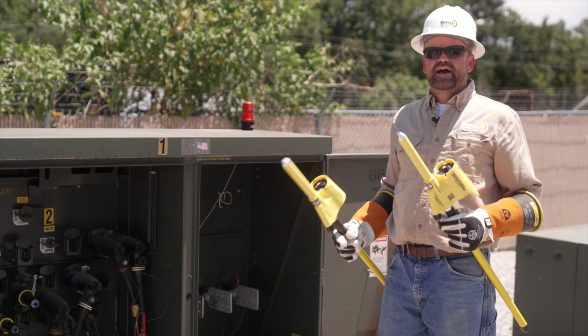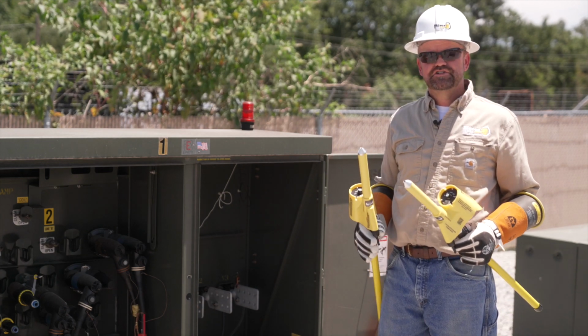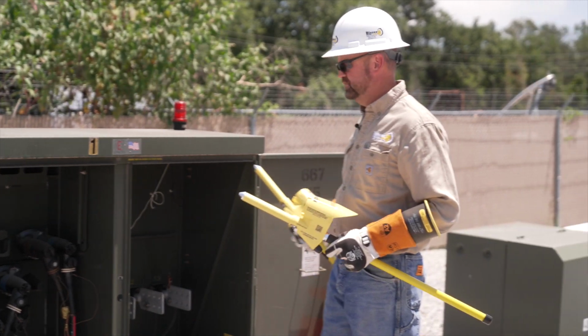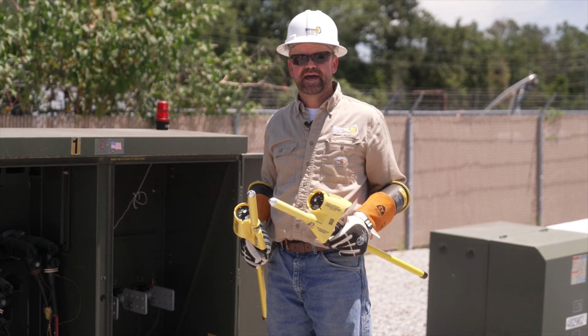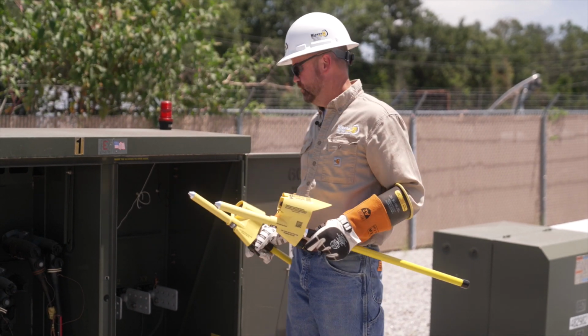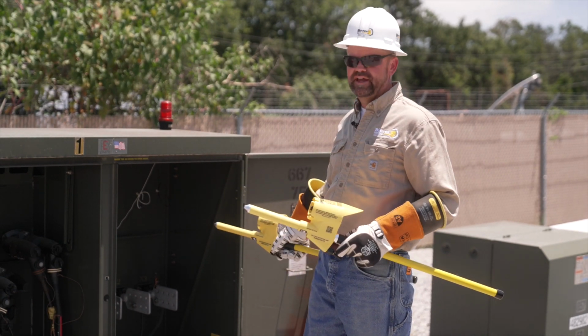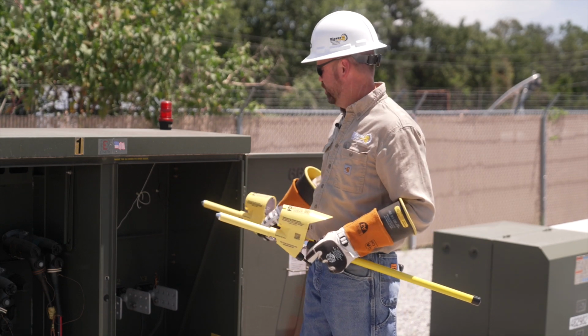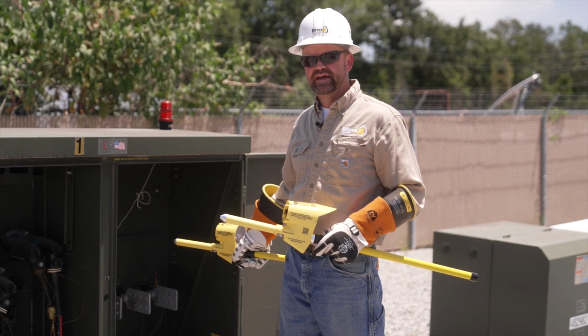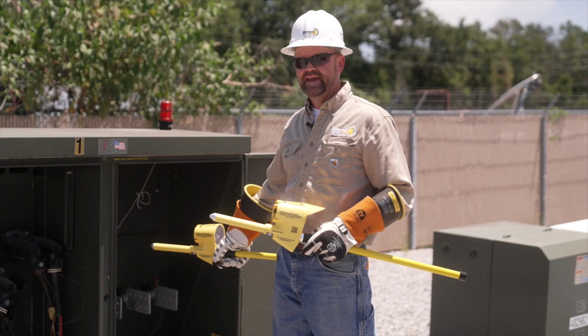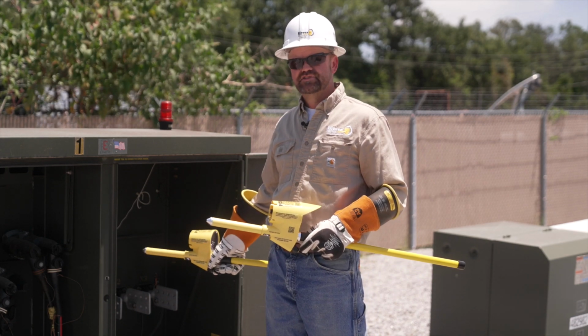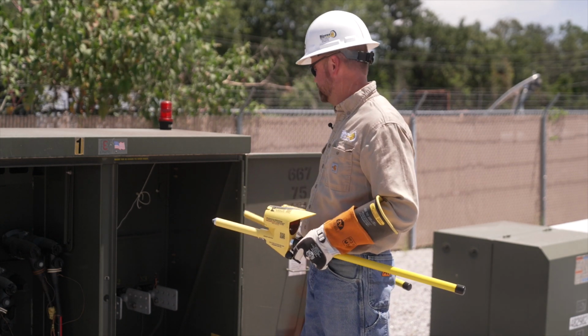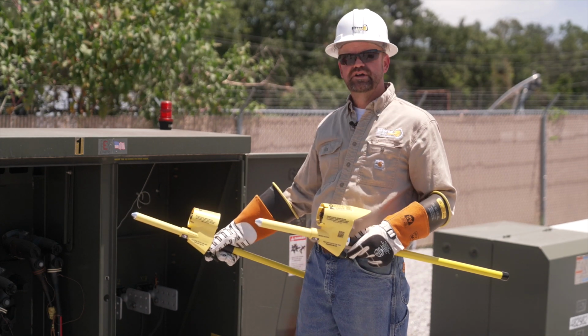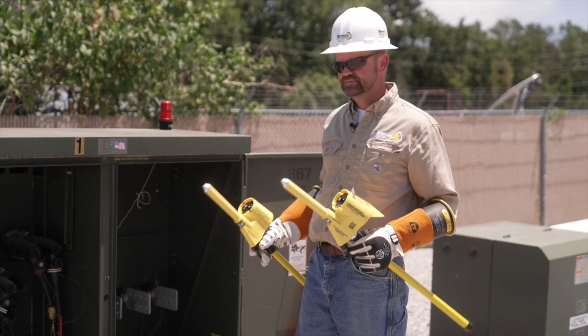So having done that, what I've done is I've not just phased these tabs, I've also developed the sequence in which these tabs are wired. In other words, I used my reference probe on the X3 bushing. My meter probe was on the X2, I had my blue light. My meter probe was on my X1, I had my red light. So that tells me my sequence is actually from X3 to X1 or right to left.